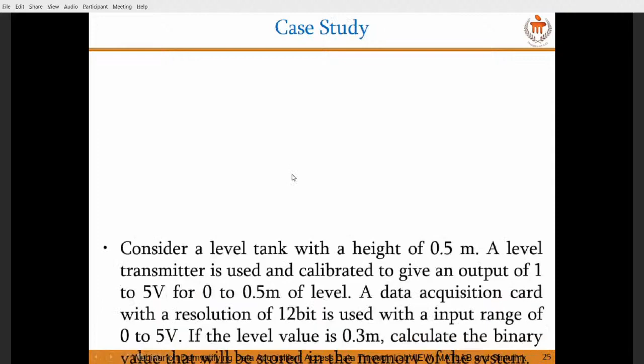You'll understand very clearly. Consider a level tank with a height of 0.5 meter. A level transmitter is used and is calibrated to give an output of 1 to 5 volt for 0 to 0.5 meters of level. A DAQ card is used with a resolution of 12 bit, with an input range of 0 to 5 volt, and the level value is 0.3 meter. Calculate the actual value that is stored in the memory of the system. Once you understand this example, almost a lot of things will be clear about the basics of this data acquisition.